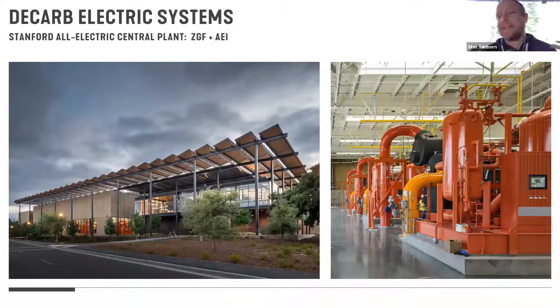But the key is adding enough thermal energy storage so that you can balance your loads throughout the project. For us, that's the equivalent of what we would do if we could do ground source geo-exchange. And there are some projects in the Midwest that have actually looked at not just ground source heat exchangers or geo-exchange, but actually doing thermal energy storage below grade by doing thermal boring, radiating your piles out to modulate the ground temperature for seasonal storage. Which can be quite cost competitive. It's like geo-exchange enhanced for more intentional temperature gradients. But again, this is a phenomenal project, an entire campus, all electric. And by definition, because our state electrical grid will be carbon neutral by 2045, this is their biggest step towards getting to carbon neutrality for their entire campus.